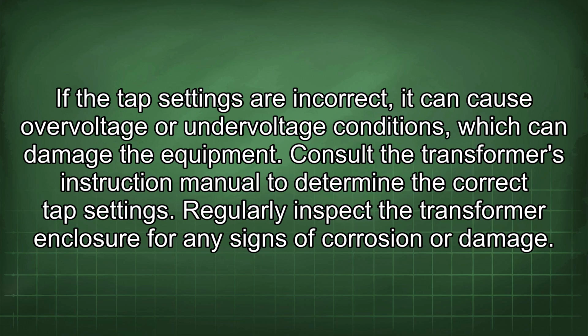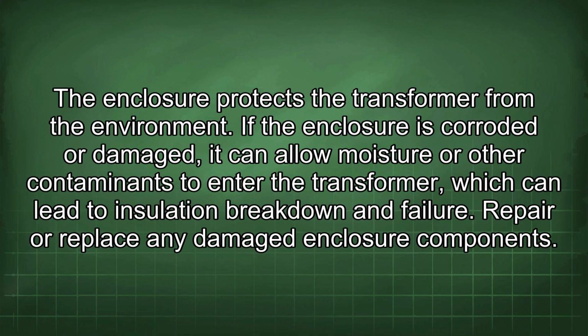Regularly inspect the transformer enclosure for any signs of corrosion or damage. The enclosure protects the transformer from the environment. If the enclosure is corroded or damaged, it can allow moisture or other contaminants to enter the transformer, which can lead to insulation breakdown and failure. Repair or replace any damaged enclosure components.